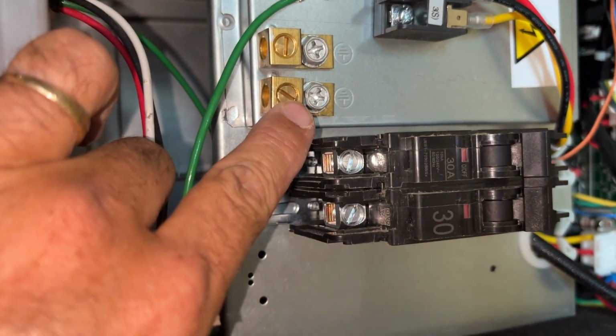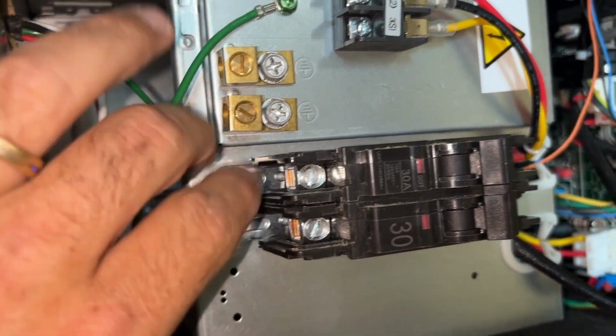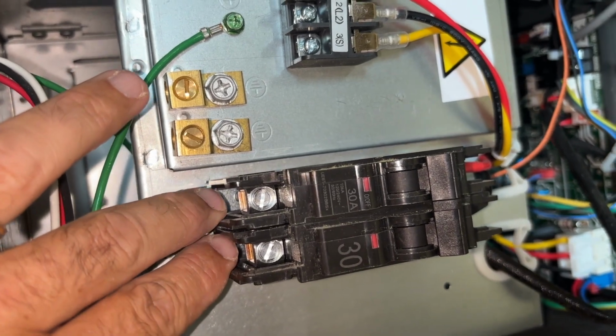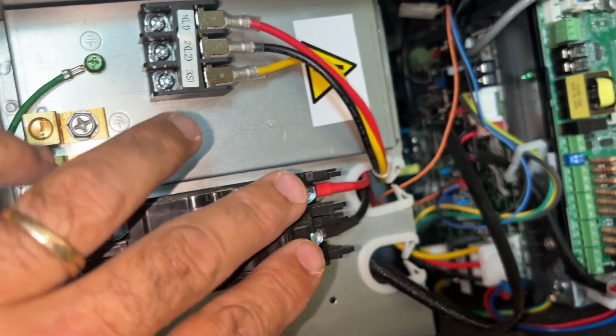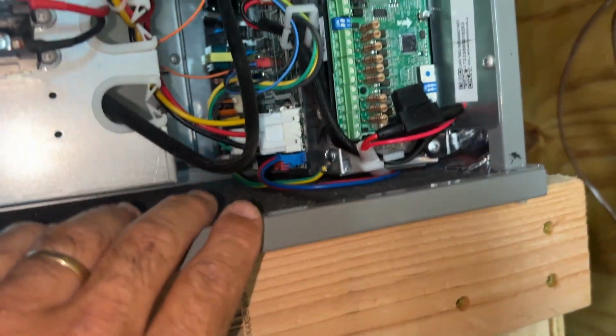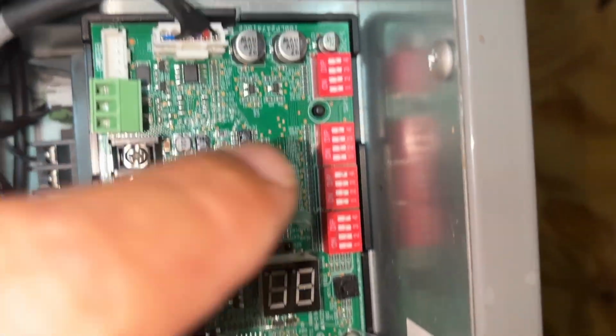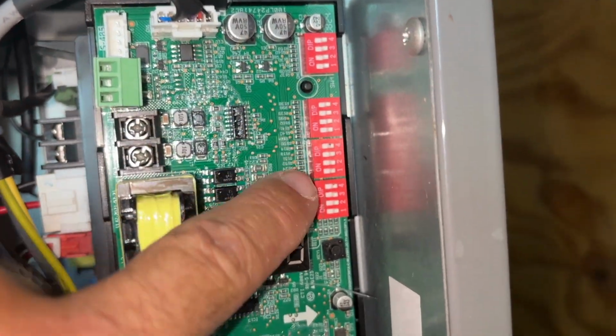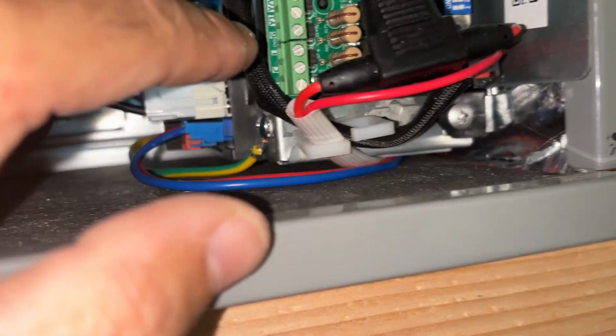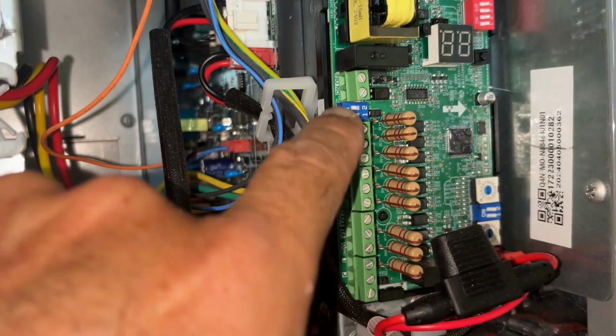And then our ground and our two lines coming in for the power for the auxiliary heat will be hooked in here. And then that's our breaker for it. And then we have all of our dip switch settings here that we need to adjust. We have our thermostat, 24 volt thermostat hookups here.